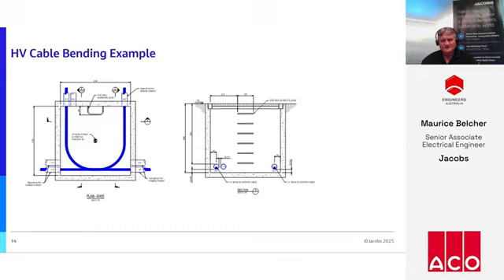The key things I'd like to note here are the digital use of the datum point in the middle of the pit, so it's physically located from a northings and eastings perspective, and the note that there are spare conduits. You can see in the bottom right image two conduits that have cables allocated and we have spare conduits. The key principle is that if you're spending a lot of money on civil infrastructure to put these pits in, the incremental cost of some spare conduits is smart engineering to ensure spare capacity.